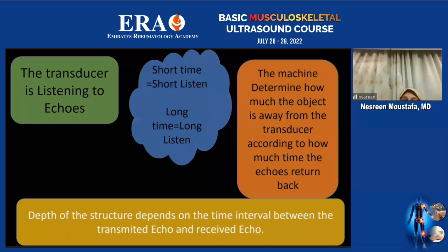The second one is that the transducer is listening to the echo. If the time for my echo to return to the transducer is short, this equals a short listen, so the echo will appear near. I will see my structure very near to the transducer and very near to the top of the screen. But if the transducer is listening to the echo for longer, I will see it farther away and deeper than in reality. So the depth of the structure depends on the time interval between the transmitted echo and the received echo.